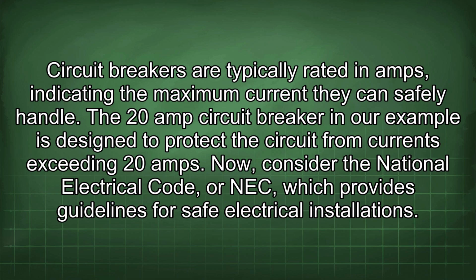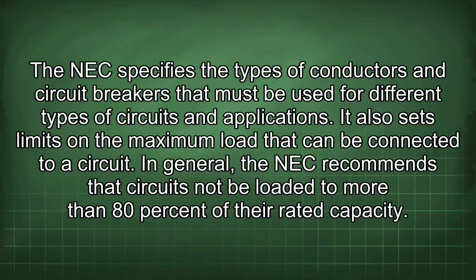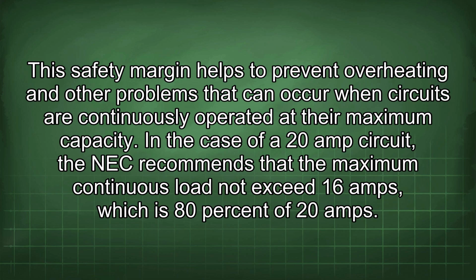Now consider the National Electrical Code, or NEC, which provides guidelines for safe electrical installations. The NEC specifies the types of conductors and circuit breakers that must be used for different types of circuits and applications. It also sets limits on the maximum load that can be connected to a circuit. In general, the NEC recommends that circuits not be loaded to more than 80% of their rated capacity. This safety margin helps to prevent overheating and other problems that can occur when circuits are continuously operated at their maximum capacity. In the case of a 20-amp circuit, the NEC recommends that the maximum continuous load not exceed 16 amps, which is 80% of 20 amps.